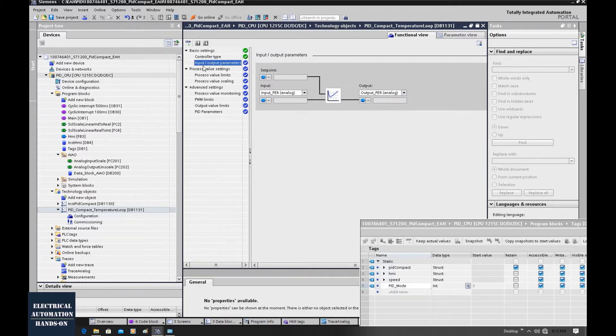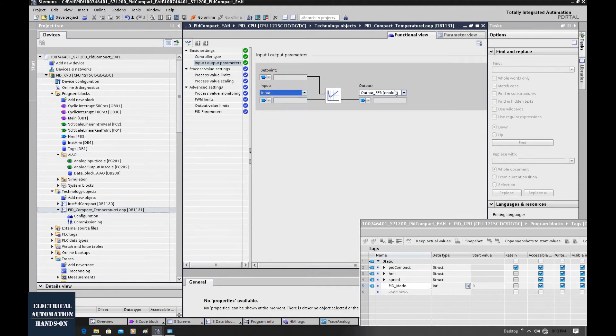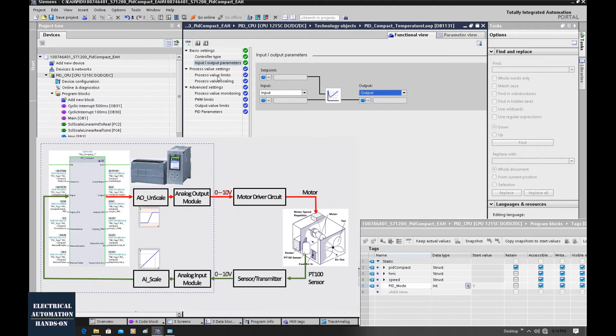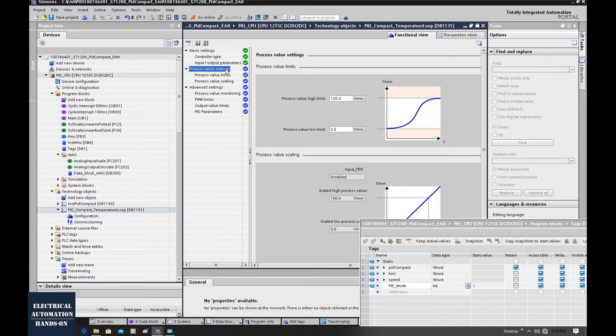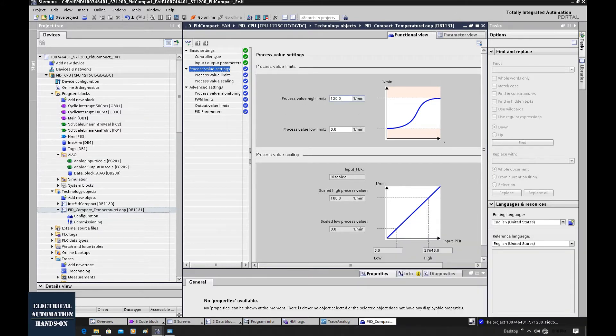Let's go to the next page — input/output parameters. Here we select which kind of input to be used for this PID. In our case, I will select the input. For the output, we will select this output. That means the analog input scaling and analog output scaling will be programmed outside the PID function block. The process value limits setting allows us to set a higher threshold and a lower threshold. When the system goes outside this range, we get an output alarm bit from this PID loop.